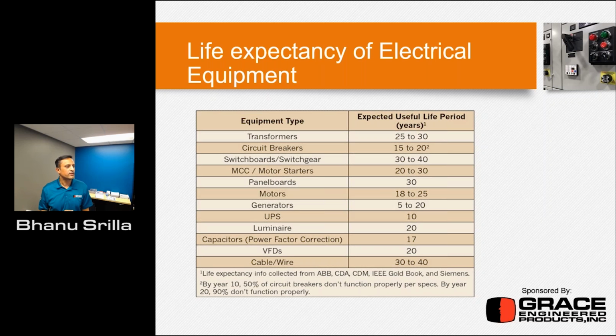Life expectancy of electrical equipment, taken from the sources IEEE, Gold Book, ABB, and CDA: transformers are designed for 25 to 30 years, circuit breakers 15 to 20, switchboards and switchgear 30 to 40 years. The reason I'm calling this out is that the expected useful life is one thing, and the actual life is secondary. The actual life depends purely on how you maintain the equipment that's been originally designed for. That brings back the question of how you maintain it on a regular basis per manufacturer guidelines or the relevant industry standards, okay?